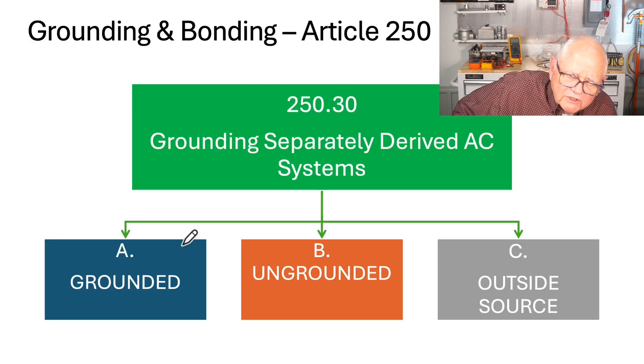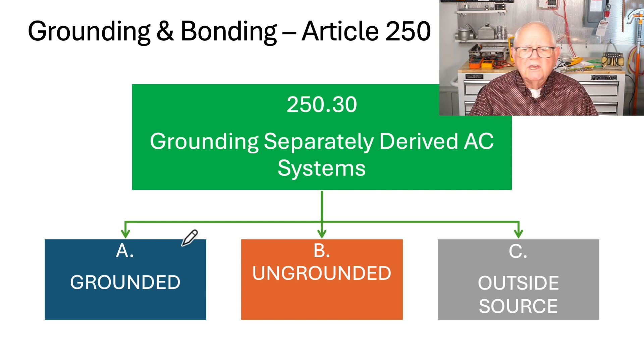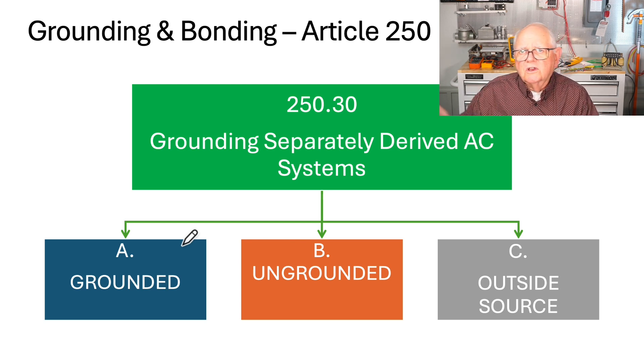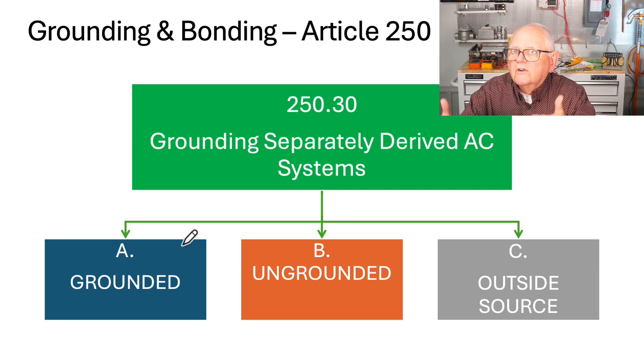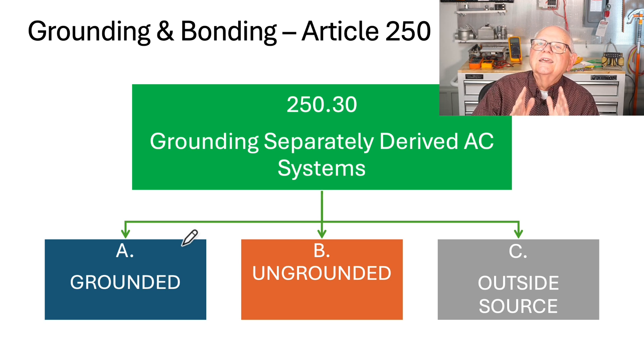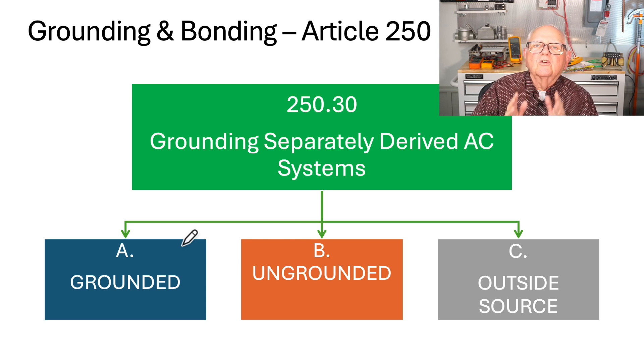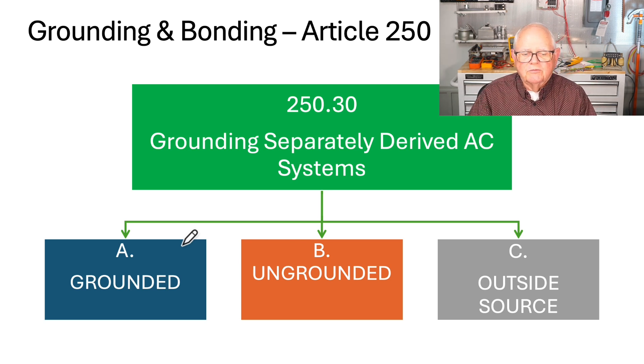Now let's look at the rules for grounding and bonding. For equipment installation, you simply follow the rules for the equipment — Chapters 1 through 4 and whatever else applies. But the real question is: if I'm not switching this neutral, if I no longer have a neutral, I have to derive a new neutral. When you have a separately derived system, the grounding and bonding rules start over again — they're not the same as for the service. You go to Article 250, Section 30: 250.30 is on grounding separately derived alternating current systems.